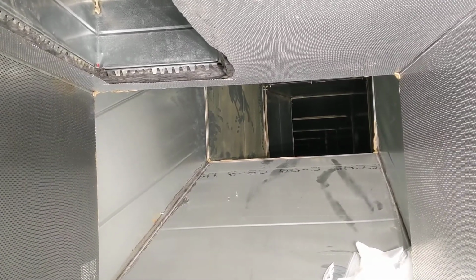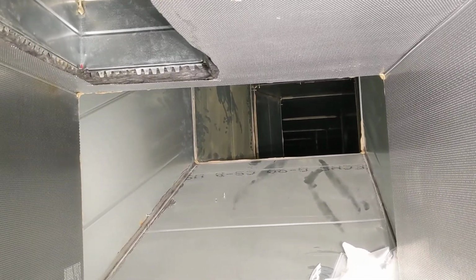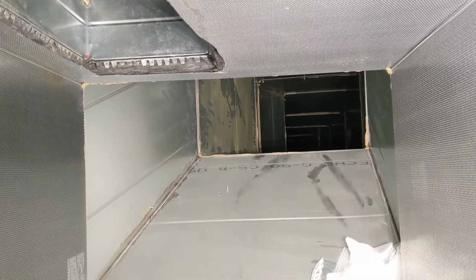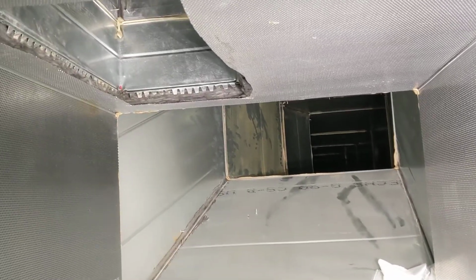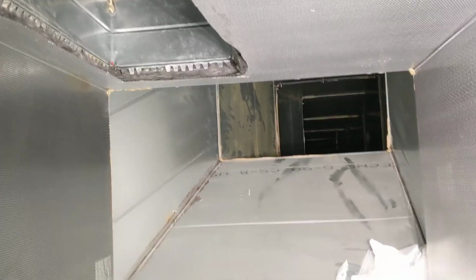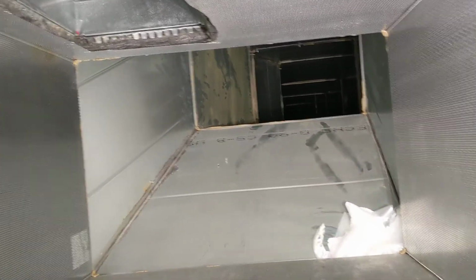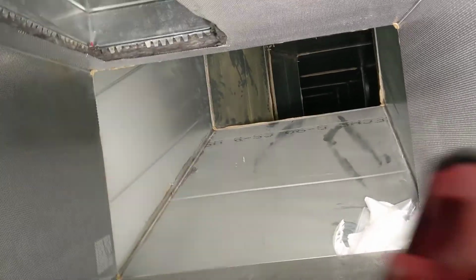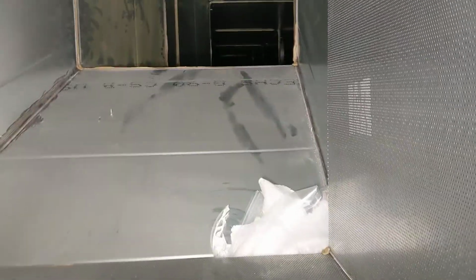This ductwork is really big. This is the main supply line, big enough to actually crawl inside and clean. So this will use the contact cleaning method — you climb inside, crawl all the way down to the end, physically HEPA vacuum and sanitize everything to get it clean that way.